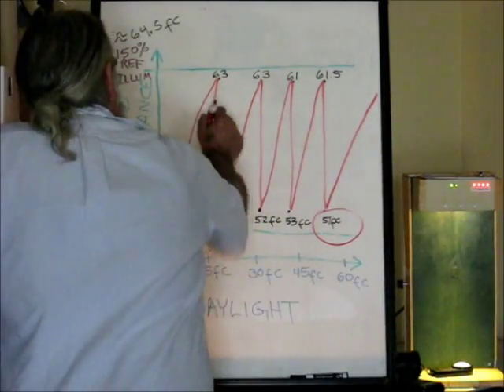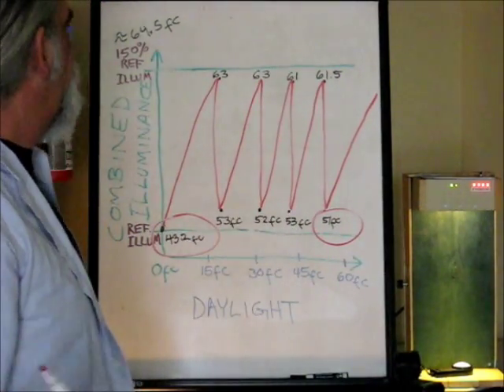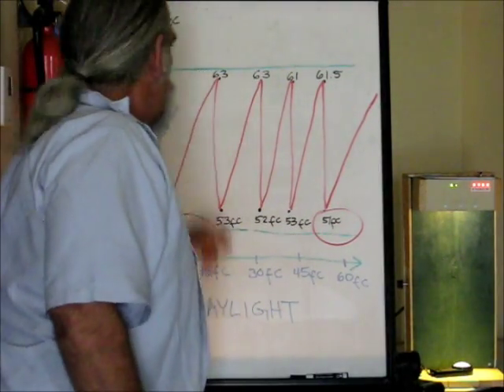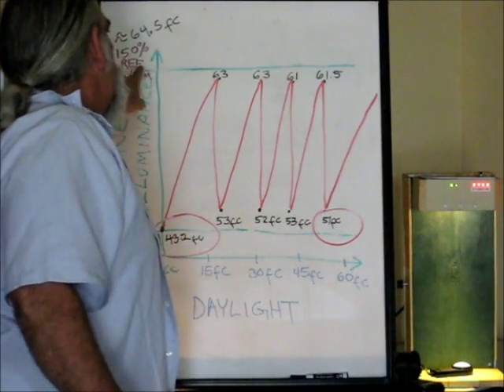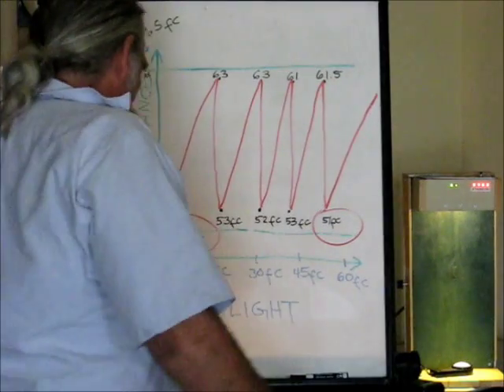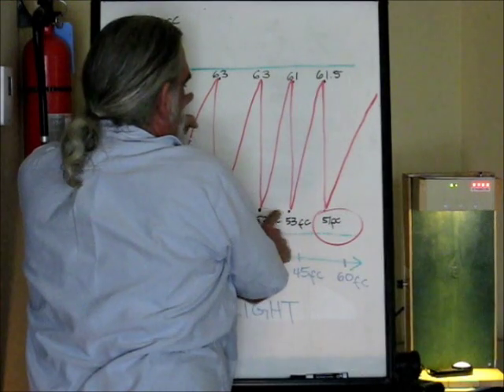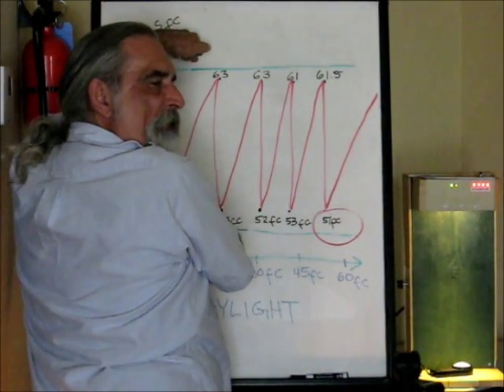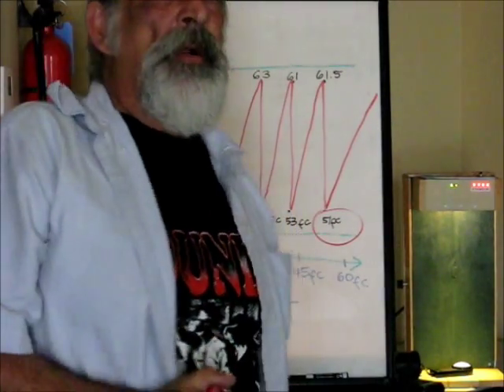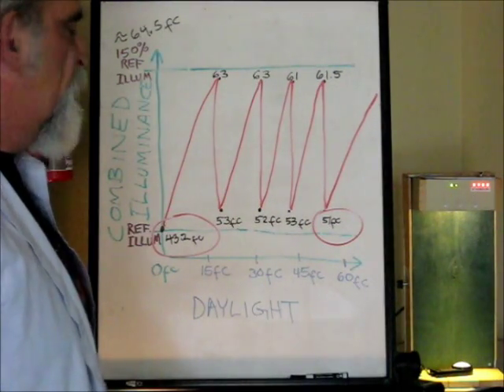Here is our reference illuminance, when there was no light coming into the area. And here is our full daylight illuminance, because there's no lights left to turn off. And here is our power reduction. 25, 50, 75, 100%. This system passes fine. It is acceptable if these switch on points exceed 150% of the reference illuminance, but they'd rather not have that. So this whole thing could actually be shifted upward as long as these snap off points remain between 100 and 150%.